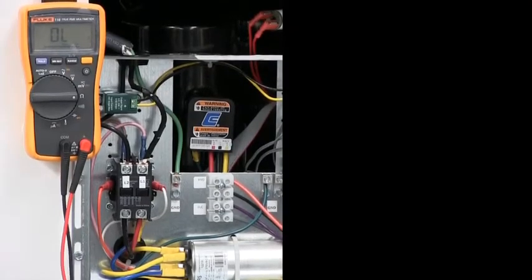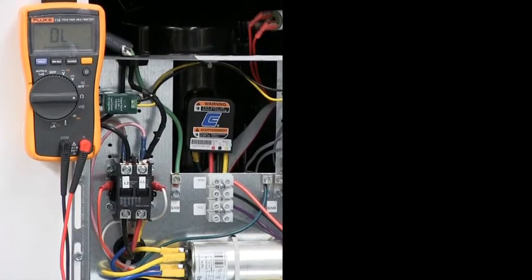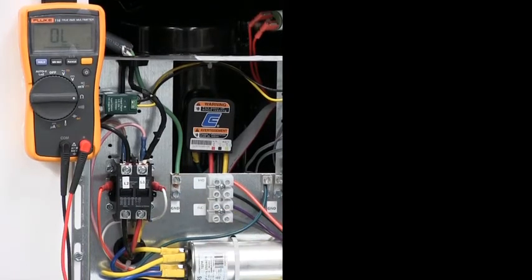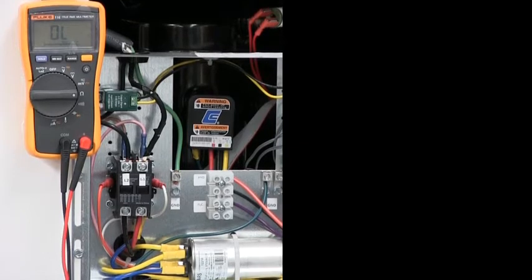To check the compressor windings, the first thing you'll want to do is make sure there's no power applied to the unit. Power would be coming in from L1 and L2. I've already checked to see that there's no voltage and the disconnect is disengaged.